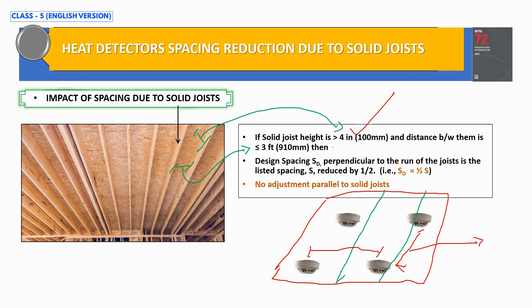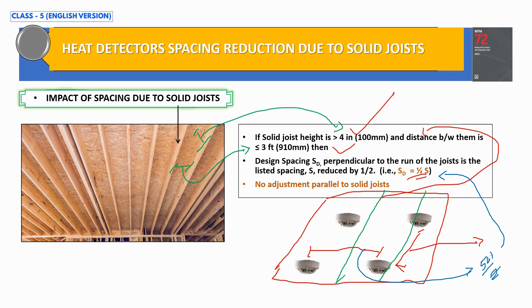If both solid joist conditions are satisfied, the formula is: SD = 50 feet ÷ 2 = 25 feet, since 50 feet is the listed spacing S as per NFPA 72. However, as per NFPA 72, there is no adjustment parallel to the solid joist — meaning that distance remains the listed spacing of 50 feet. So the spacing perpendicular to solid joists is SD = 25 feet, while the spacing parallel to solid joists remains 50 feet.